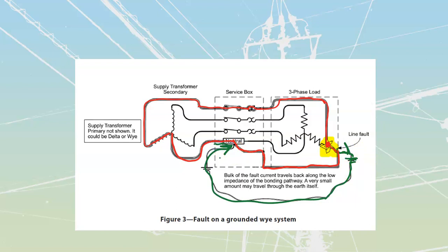Overall, when I take a look at this, I see that I am going to have a massive amount of current that is going to flow, because I know that I is equal to E over R. I've got whatever my value of voltage is over here. It could be 120/208, 600, 347, but it's going to be over top of a very low value of resistance. And so therefore, we have a high value of current, and that high value of current flowing through this path is going to trip out that breaker. As soon as it trips that breaker, it's going to interrupt that current path. This is what we want. We want to create, really quickly, a large current that is then going to trip the breaker.